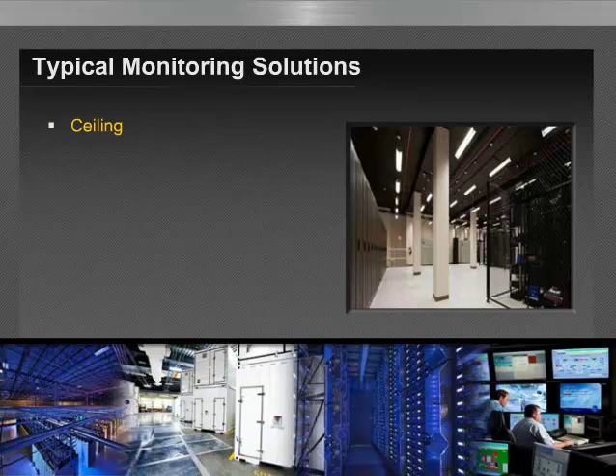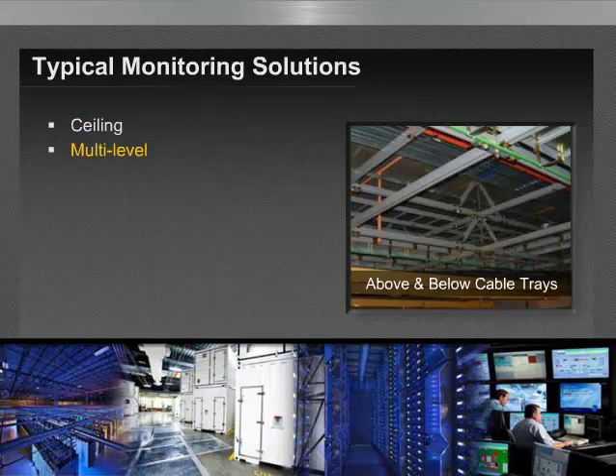And here's multi-level detection, the idea of detection at the ceiling and below cable trays. And the idea is that we're still providing very early warning fire detection under the scheme where we're sampling 200 square feet, but alternating every 400 square feet, 200 square feet between sampling port high and low, with the ability to detect below obstructions.